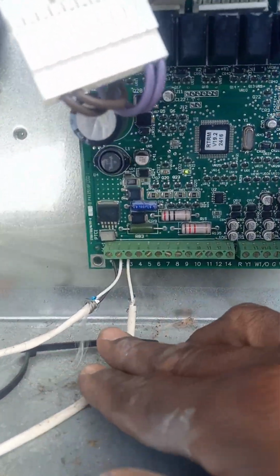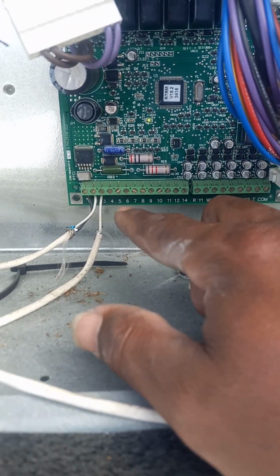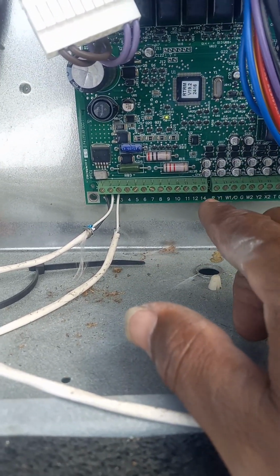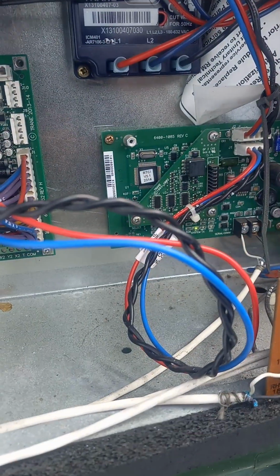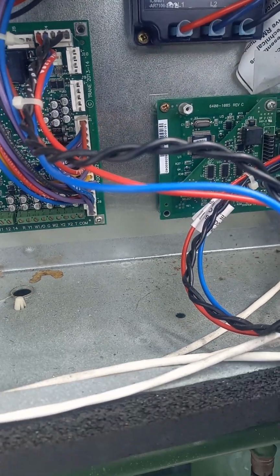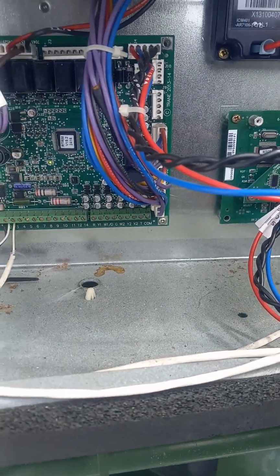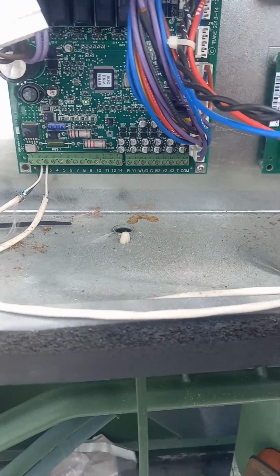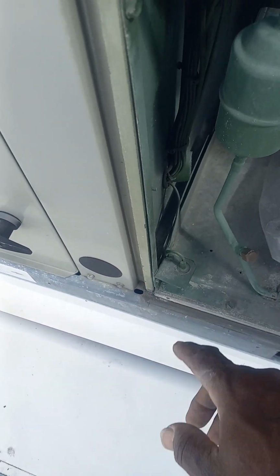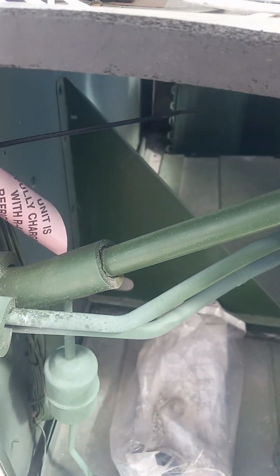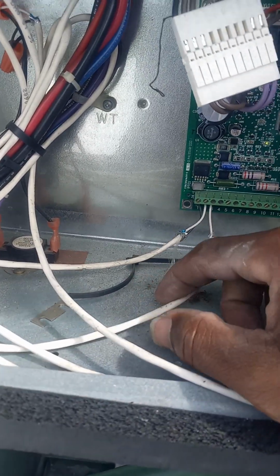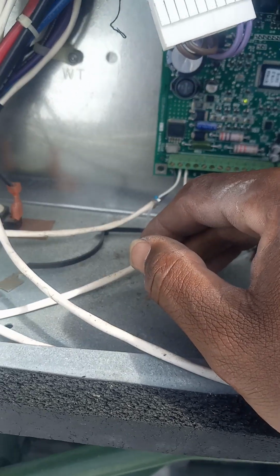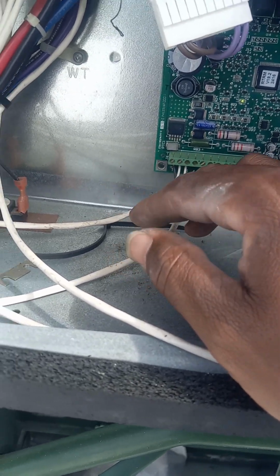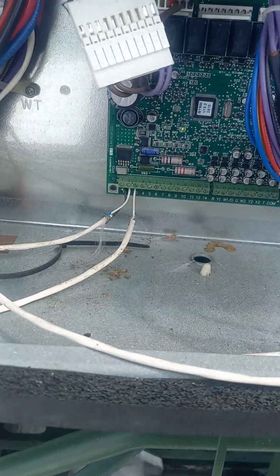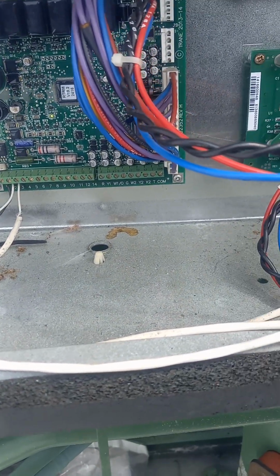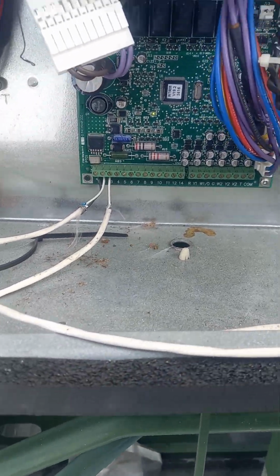Alright. On here you can see these terminals. There are different components that can be connected to this board. Because we're using the Trane communication board, when you log into it, you can see everything that's going on with the unit. On this board you have sensors and all different types of stuff. This is an outside air temperature sensor, and then you have an indoor temperature sensor. This is the supply and the return sensor wires. When you log into the system, you're going to see the temperature of the unit and the space temperature and all that stuff, and then it goes from there. So that's the basics where the low voltage is concerned.